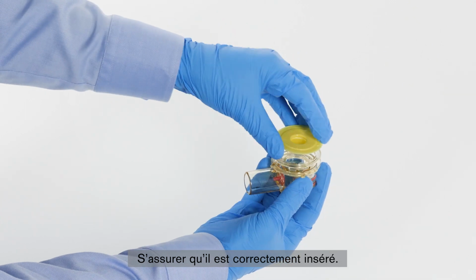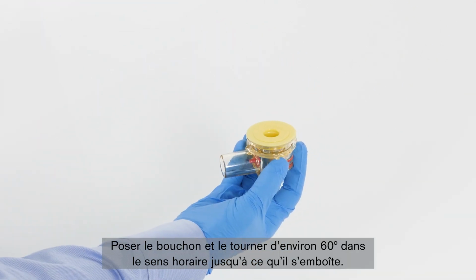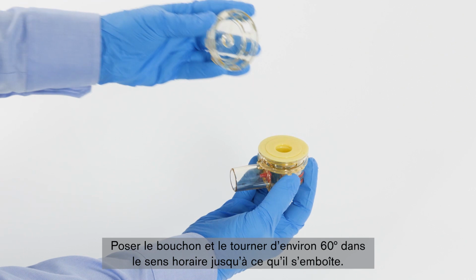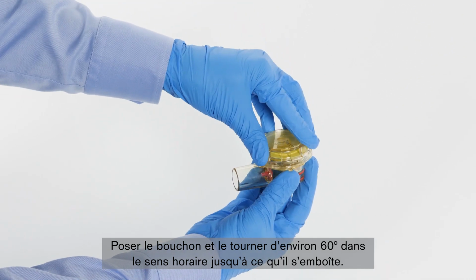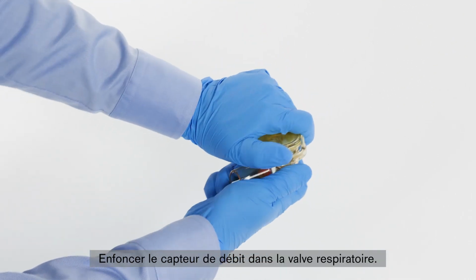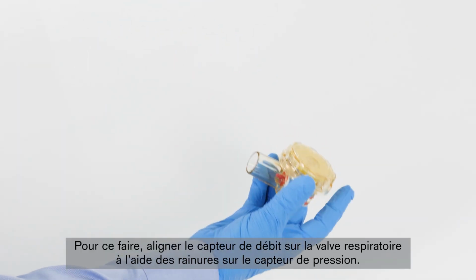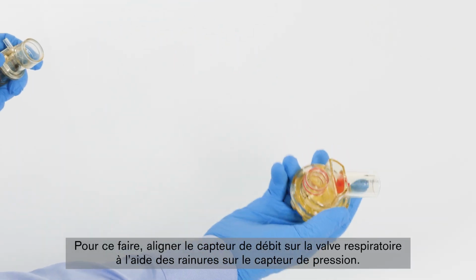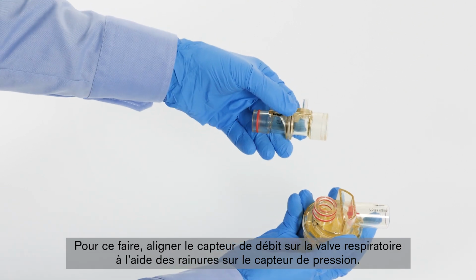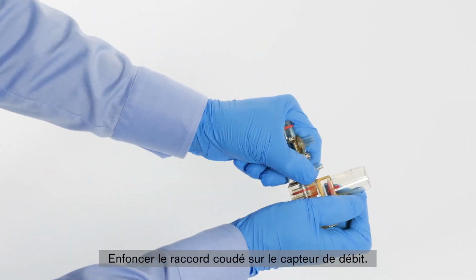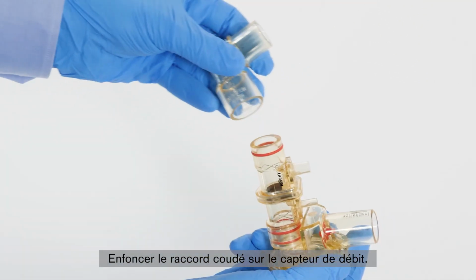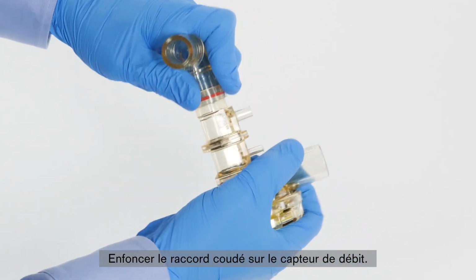Place the diaphragm in the breathing valve housing. Make sure that it is fitted correctly. Mount the cover and turn it about 60 degrees clockwise until it engages. Push the flow sensor onto the breathing valve. To do so, align the flow sensor on the breathing valve using the grooves in the flow sensor. Push the elbow onto the flow sensor.